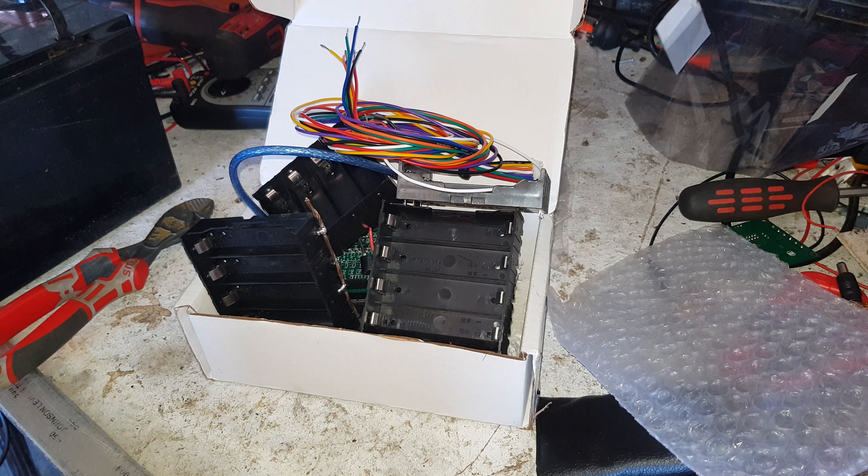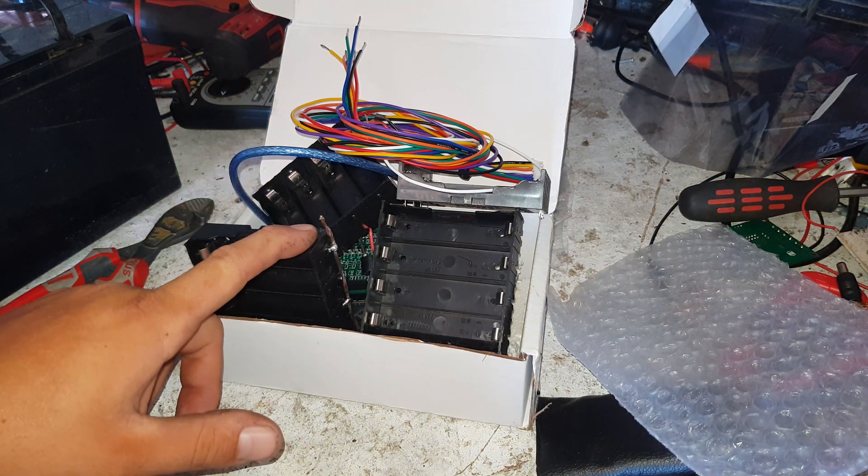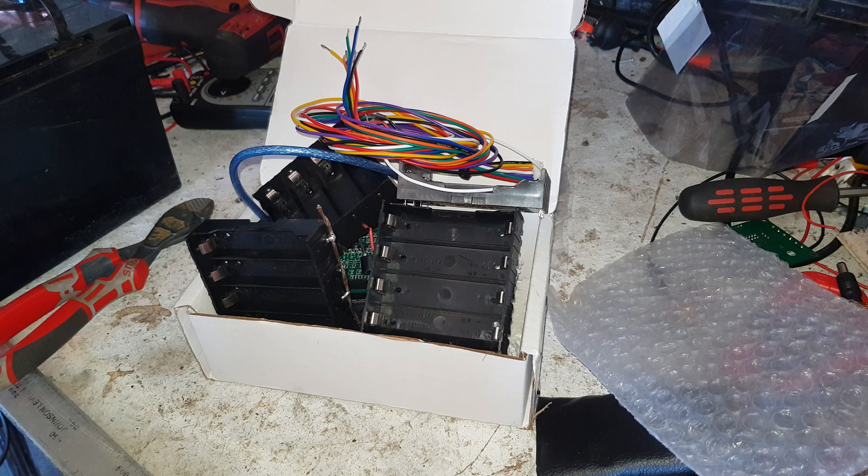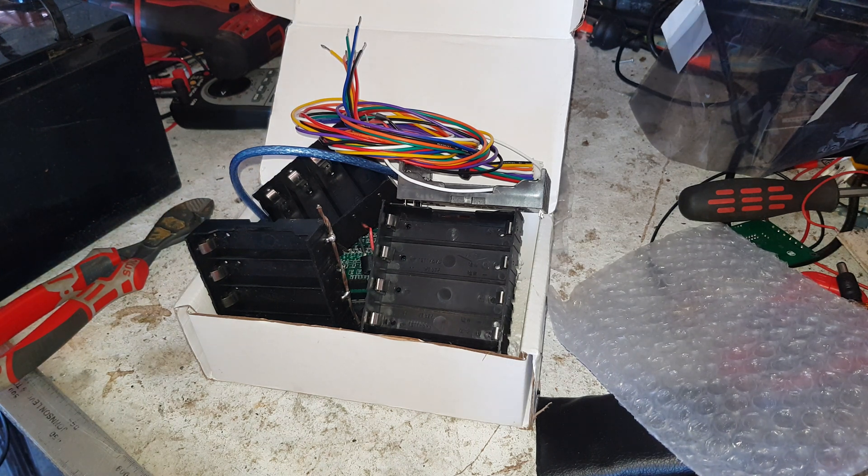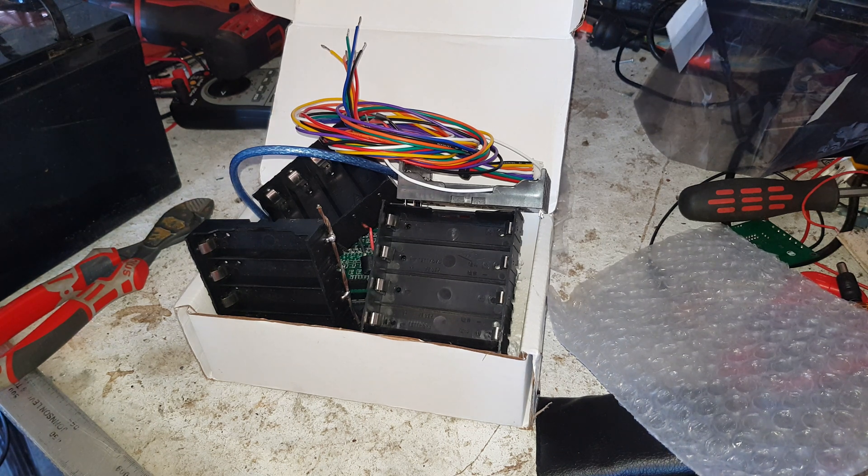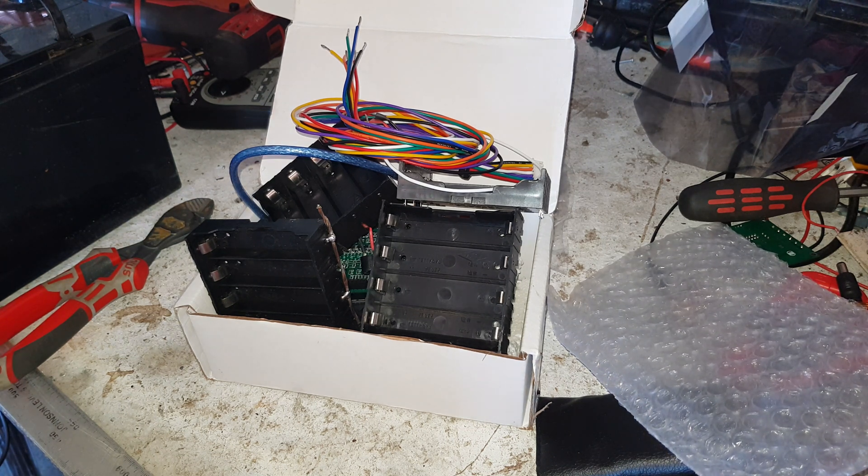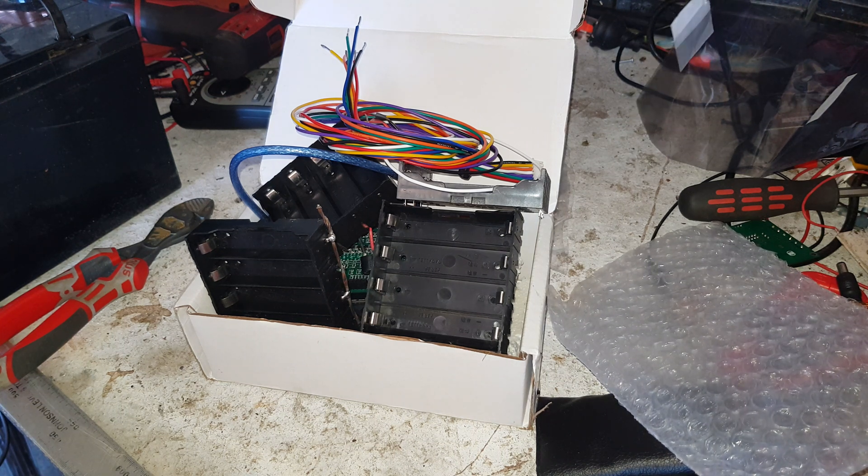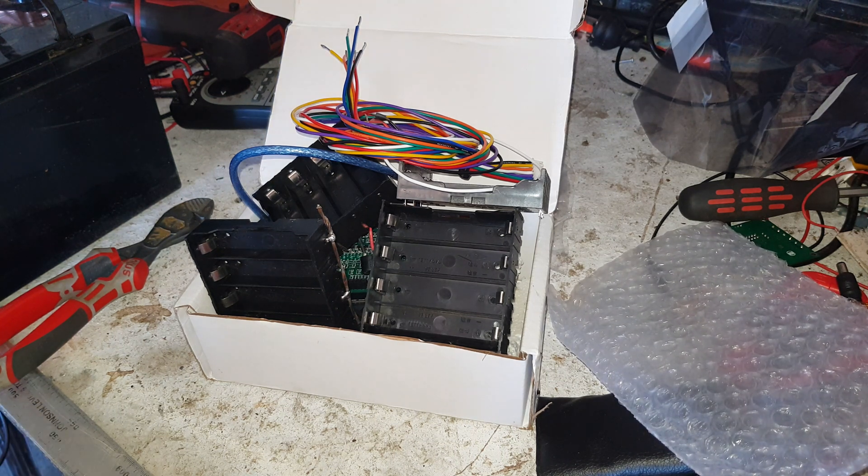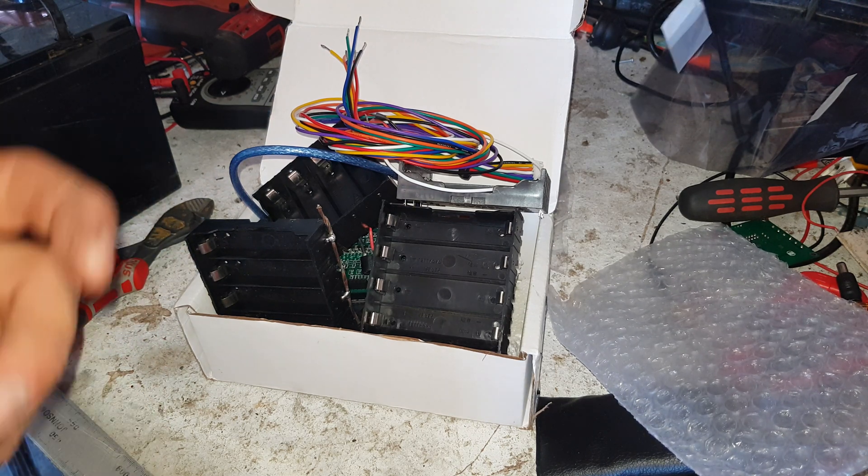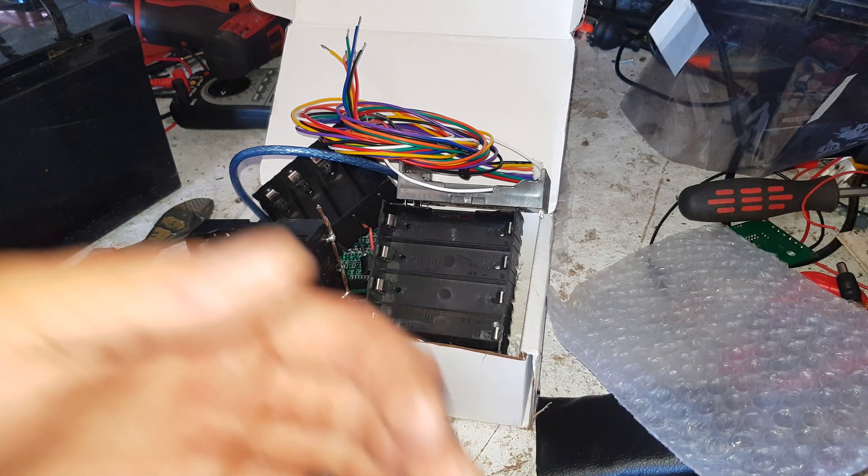So what we'll also be able to do then is tap a separate charge controller off the existing incoming. And the 12 volt pack can be charged. What happens like now is when it starts getting full, I know you can't see the charge controller but I'm looking at it, charge controller sitting at 34 volts. So we can easily charge a 27 volt 7S pack, happy days. So we've got even now we're not capturing all the energy we could be capturing, and that's with the 20 kilowatt bank. I'm not using enough power out of it, I need to use more, which means I may need more storage.